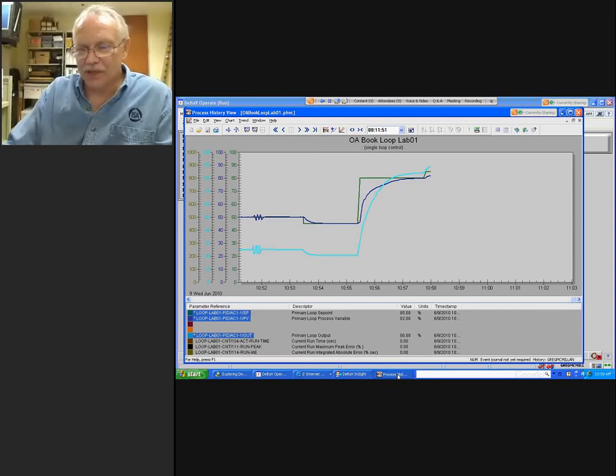What we have here would be what you would normally see in the field, where the controller was tuned for the worst case, the high process gain, which occurs for low pressure set points, and therefore the response is sluggish for the high pressure set points where you're on the flat part of the pump curve. Well, it looks like we're going to get there. It's just going to take some time. So let's go down to region one where things are faster and do that by lowering the set point significantly.